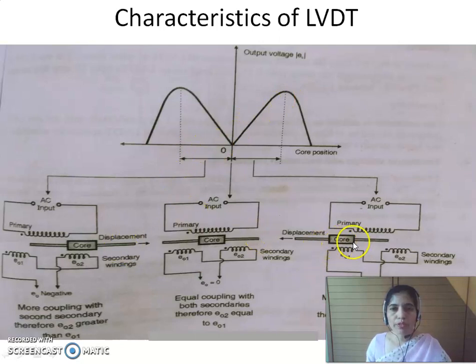Now, if the core moves still further away from one of the secondaries, that is, as if it is moving outside the cylinder, and there is no overlap between the primary and the secondary, then also the voltage will go on reducing on the other side. Therefore, the voltage peaks at a point when the core is exactly above one of the secondary windings, but as it moves further away from the secondary outside the cylinder, the induced voltage further reduces. Therefore, we get the other half of this particular characteristic.